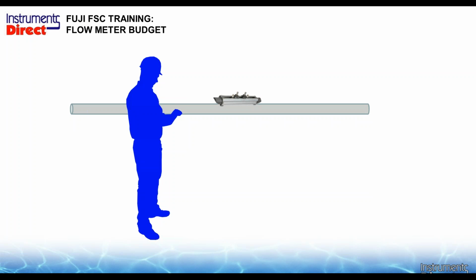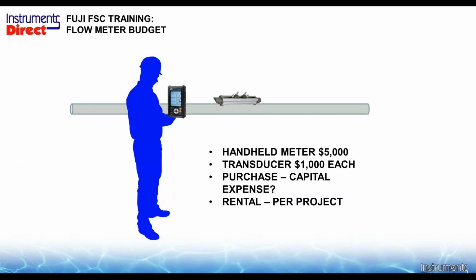So what's it cost? Well, a portable ultrasonic transit time flow meter, you have a choice in some cases of multiple transducers, but most applications have a single transducer, and we'll see those in a moment there. The handheld device is about 5,000 bucks. A transducer is about 1,000 bucks. The base price for a Fuji right now is about $6,149 for a flow meter and a set of transducers.